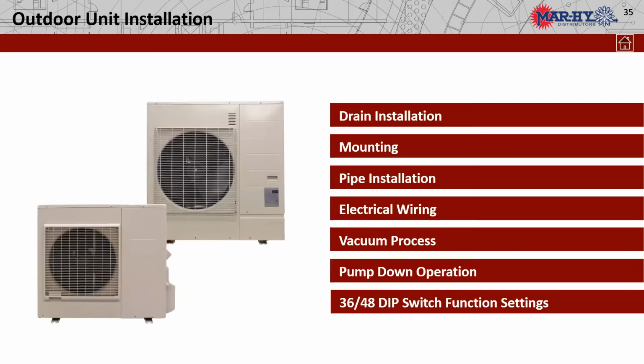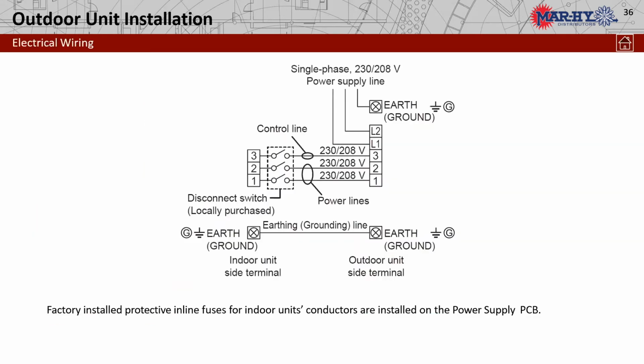Okay, let's check out our outdoor unit installation. Boy, they're beating this to death, huh? Line 1, line 2, outdoor unit connections, and then our 1, 2, and 3 to the indoor unit. That is our mini split connection. No difference.